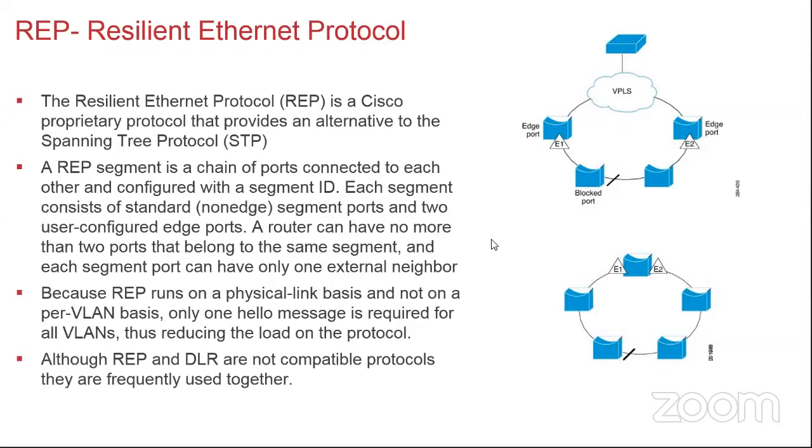So typically what we'll see here is REP is one of the easiest methods of being able to tie in multiple switches in a ring. But again, you'd be looking at reconvergence time, so how long it takes the switch to reconfigure your connection from one point to another. That could be anywhere from 50 milliseconds to about 250 milliseconds, depending on a number of different variables that go on inside of the switch.